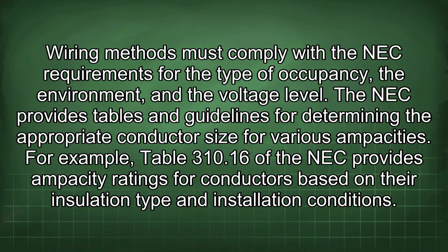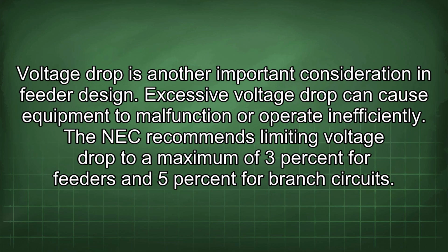Wiring methods must comply with the NEC requirements for the type of occupancy, the environment, and the voltage level. The NEC provides tables and guidelines for determining the appropriate conductor size for various ampacities. For example, Table 310.16 of the NEC provides ampacity ratings for conductors based on their insulation type and installation conditions. Voltage drop is another important consideration in feeder design. Excessive voltage drop can cause equipment to malfunction or operate inefficiently. The NEC recommends limiting voltage drop to a maximum of 3% for feeders and 5% for branch circuits.